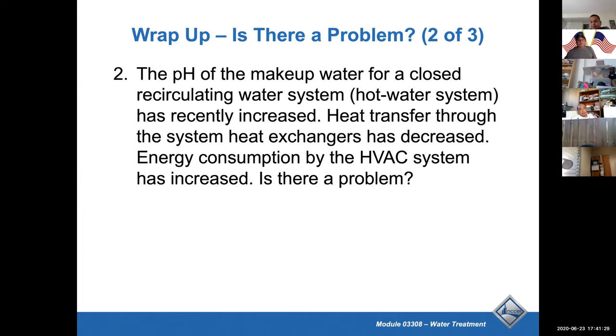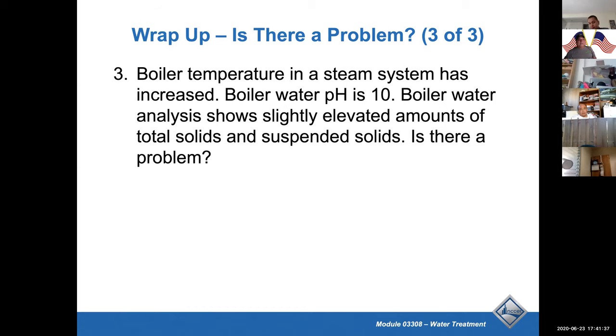pH of makeup water for a closed recirculation system has increased. Heat transfer has decreased. Okay. Is there a problem? Yes, you're building up scale. And boiler temperature in a steam system has increased. Boiler pH is 10. Cycling elevates total solids, but is there a problem? Yes.